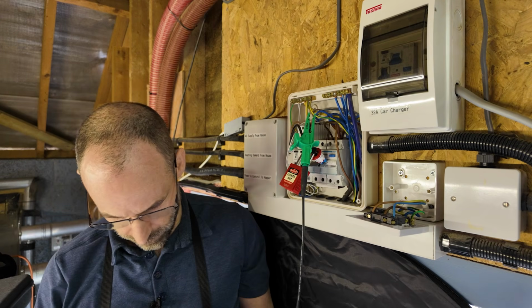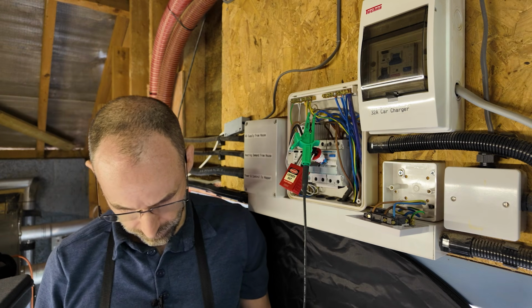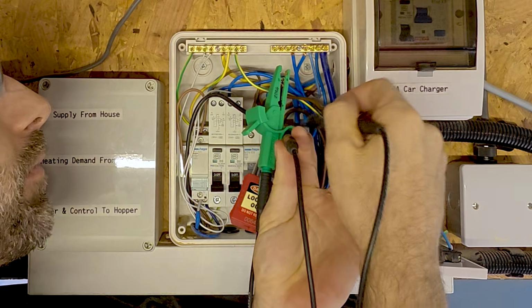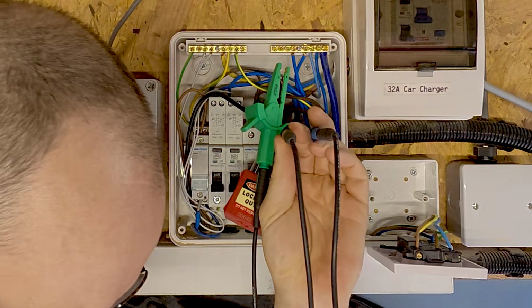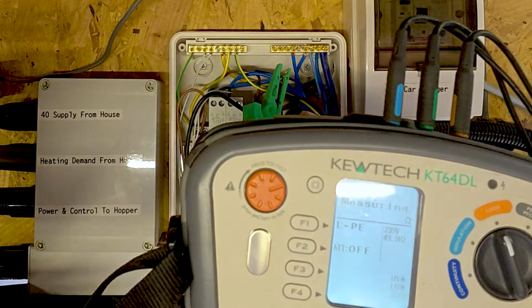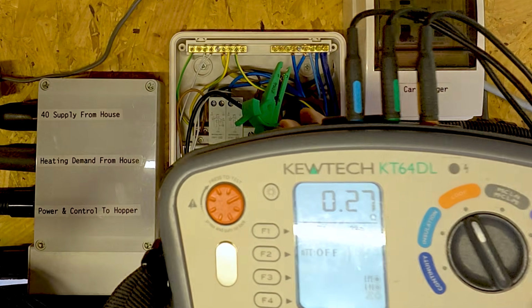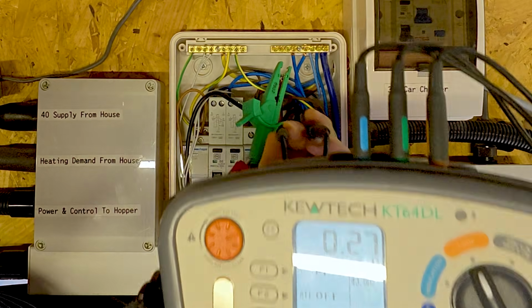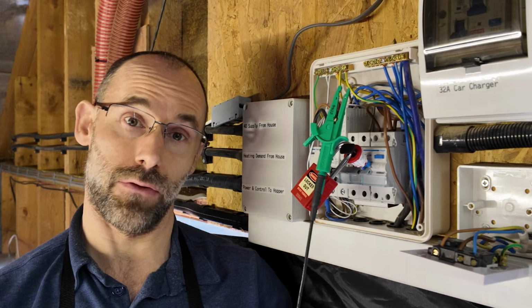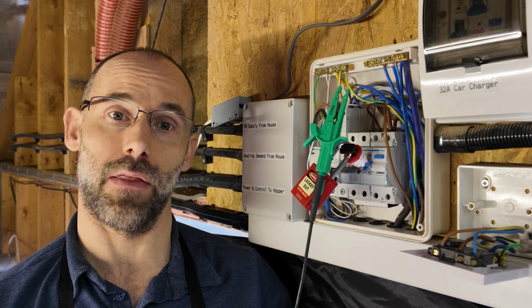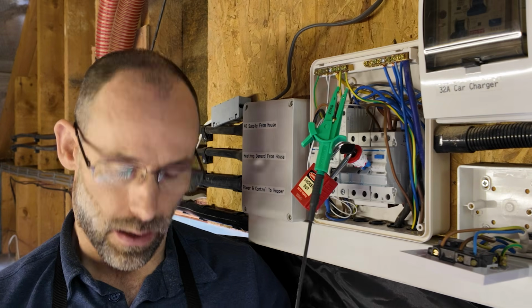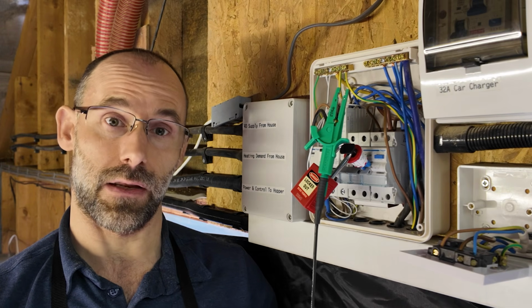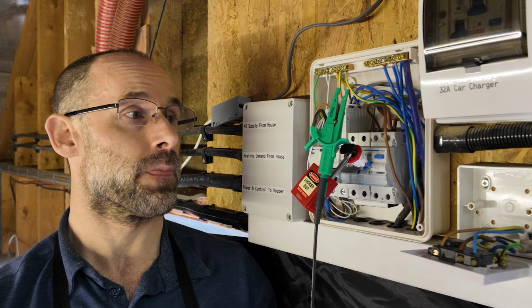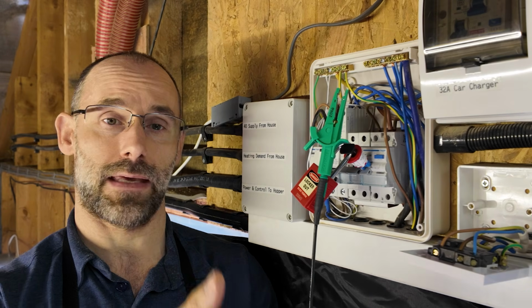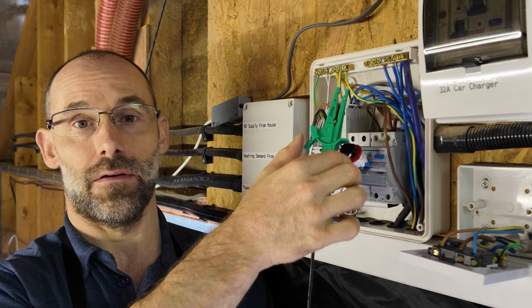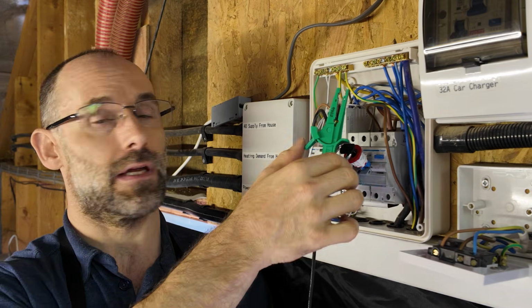I get into something called an earth fault loop impedance mode on my tester. I come onto it, and my meter is going to detect that there's voltage there, and with any luck, it'll give me a reading. There you go, 0.27 ohms. Now, this is where you need to know something about the earthing arrangement and the regulations, but that's a pass for us, basically. There is little enough resistance that current can freely flow in the case of a fault and trip out the GFCI or the RCD. Cool.